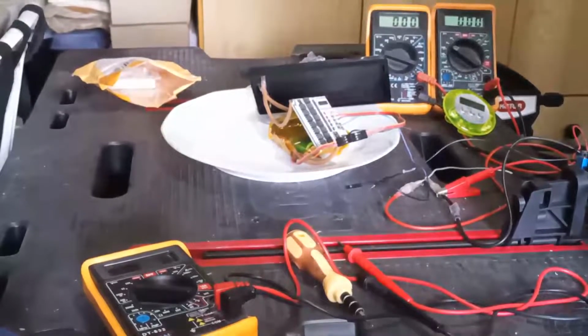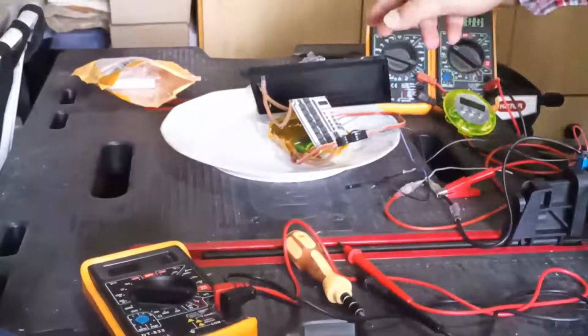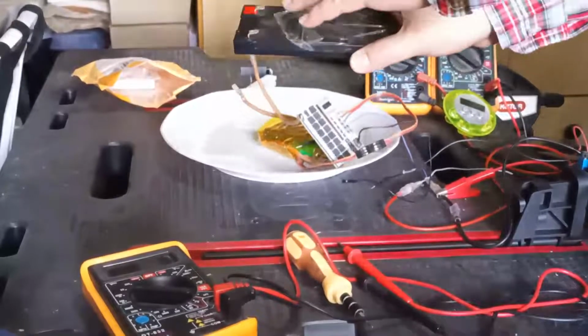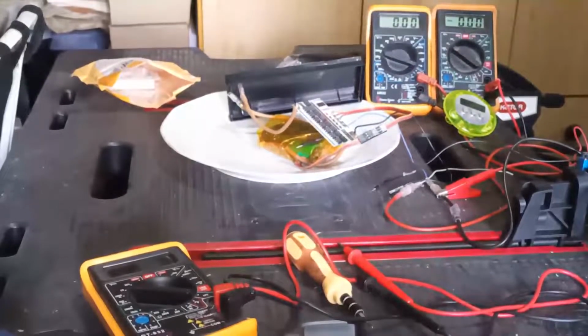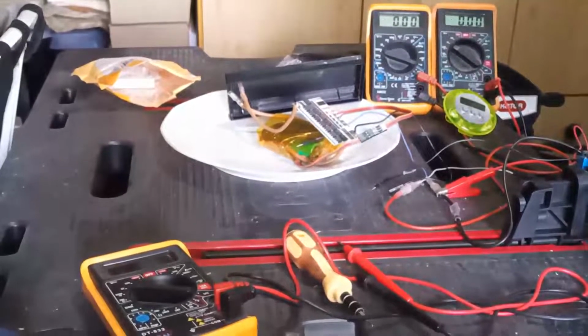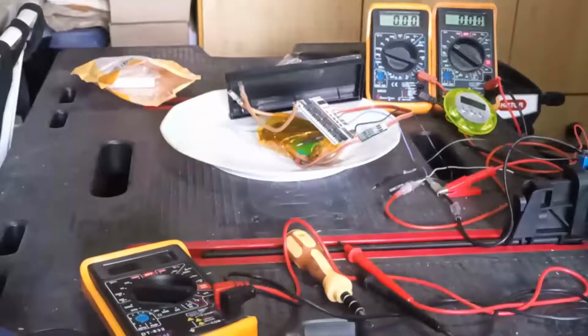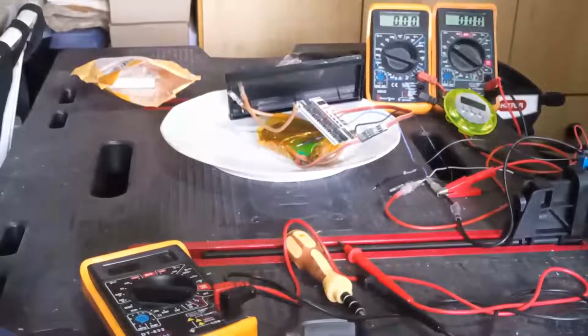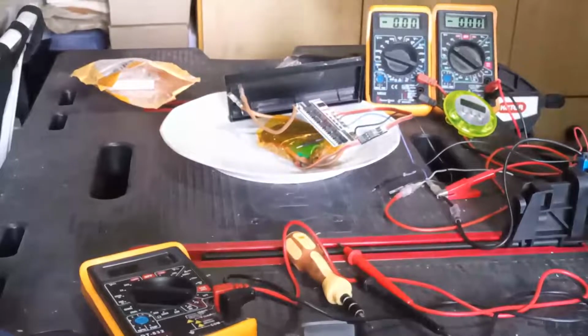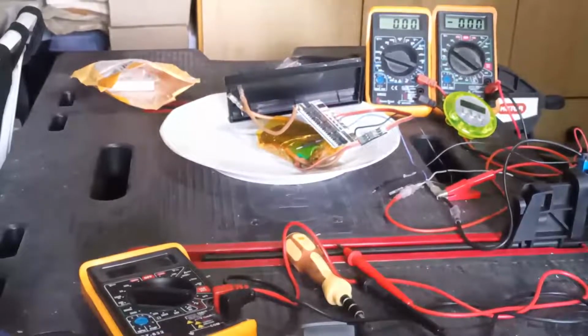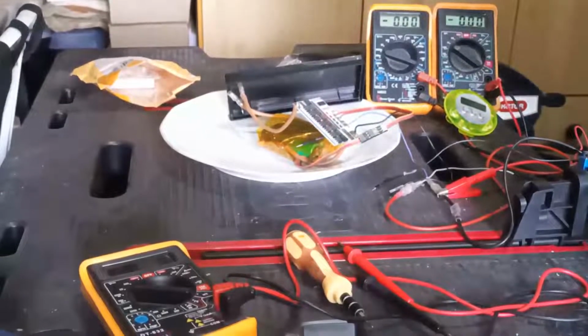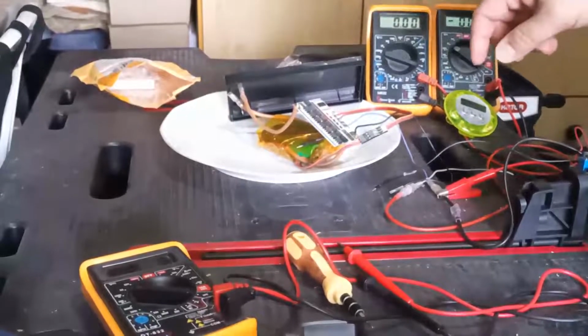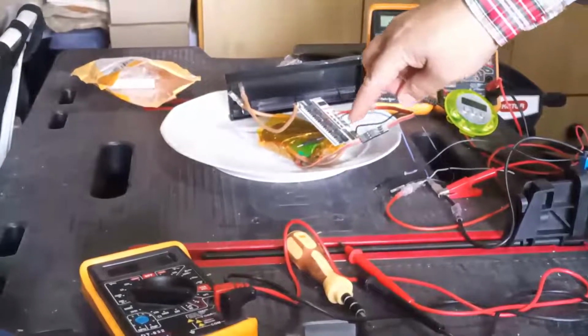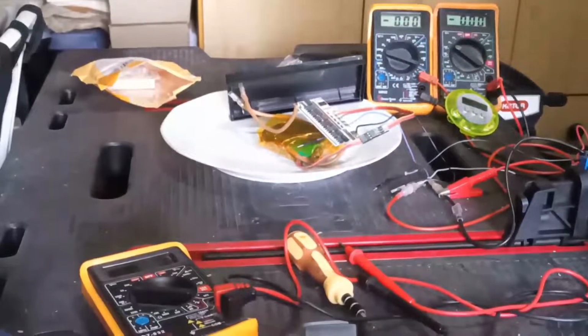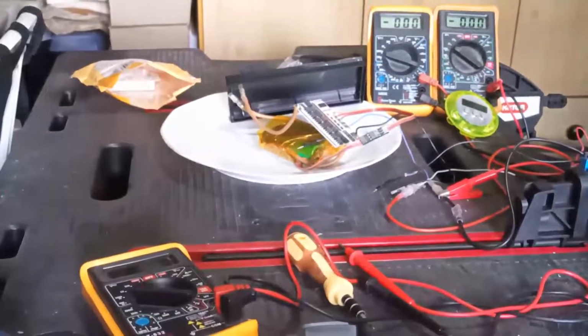To do this, we need to leave the BMS connected and try to charge it using the main charging, like it was a battery being charged, and just see if it cuts the current in the middle of the charge while we're overcharging. Notice that the balance current of the BMS is only 60 milliamps, meaning it could deal with 60 milliamps, but in this case its bypass resistors, which are over here, will not be enough because the current fed will be a lot more than 60 milliamps.